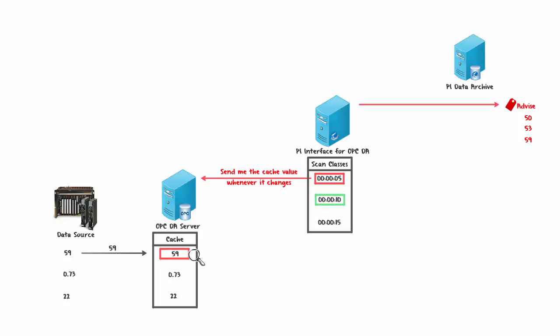For the second Scan Class, if the PI Interface for OPC DA finds a Polled Point, it makes a request every 10 seconds for the Cache Value on the OPC Server. The first Cache Value of 0.73 gets sent to the Polled Point. Ten seconds later, the PI Interface makes a new request, but if the Cache Value hasn't changed, this 0.73 is again sent to the Polled Point — and again 10 seconds later if there's still no change.